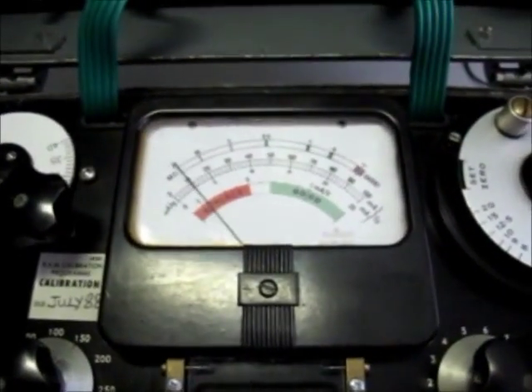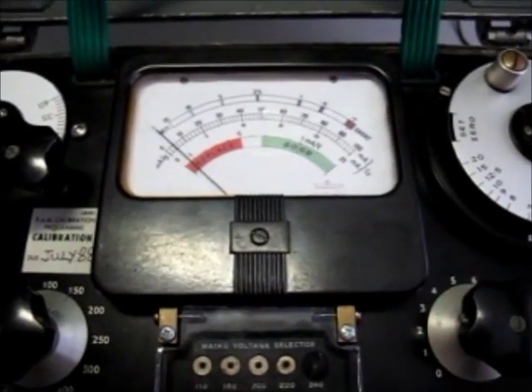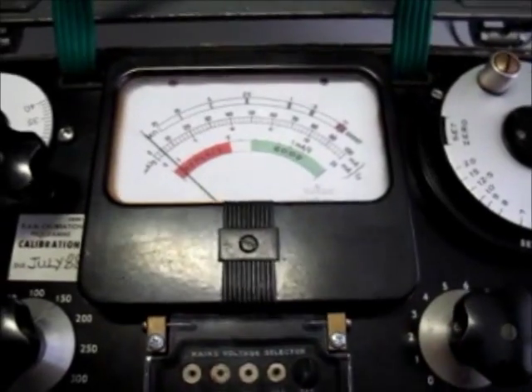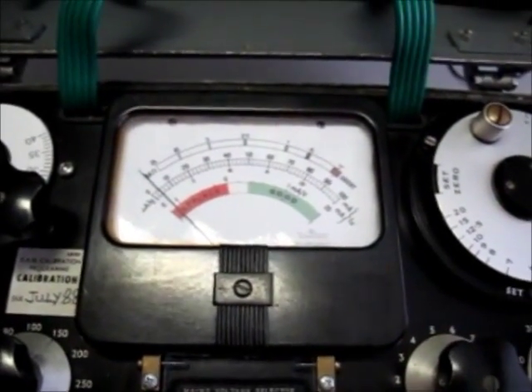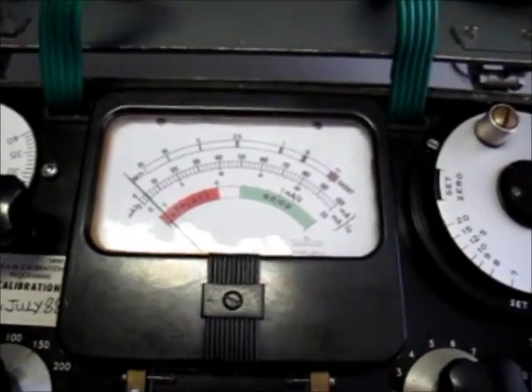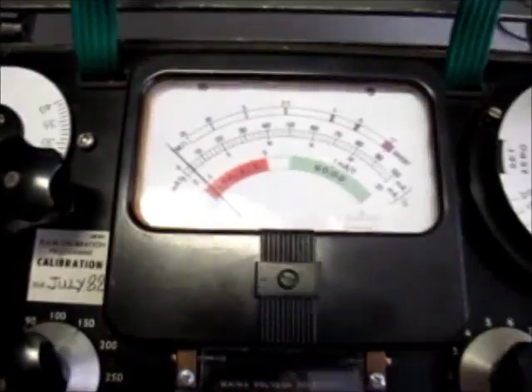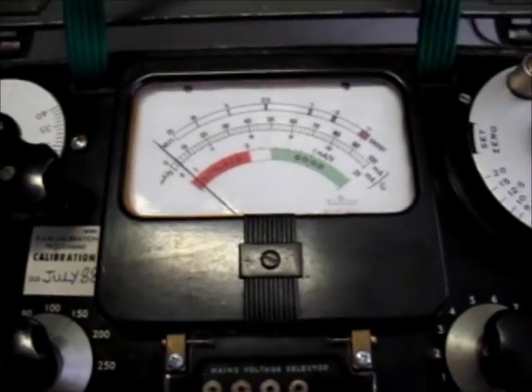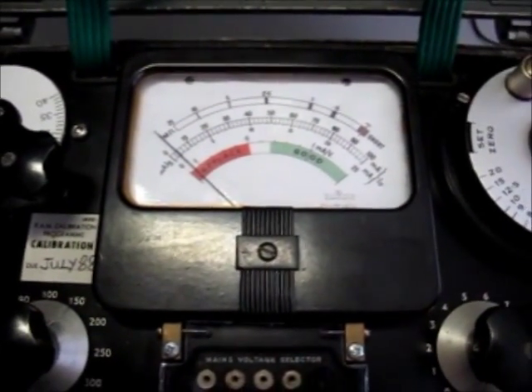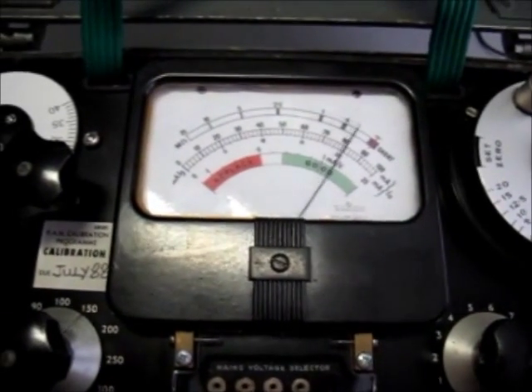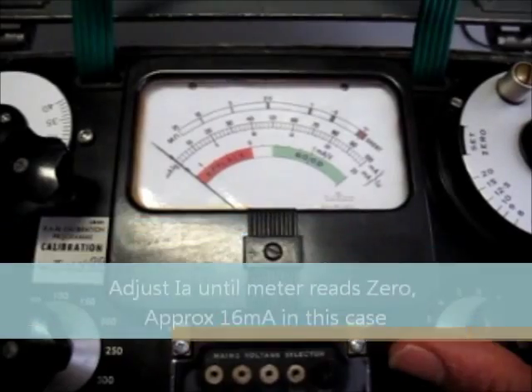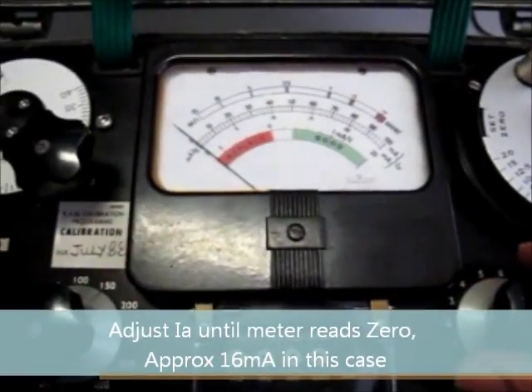We'll then go through a number of anode tests, and we'll try to make sure the meter stays higher than 25 milliamps. So all these are anode correction electrode to electrode tests. And finally we'll do a heater test. Now we're going to see the heater's now starting to come on inside. And now we're really going to do our test. Now the minute you kick to this section, the meter will go up or down, and you're meant to zero it. So we'll just go there, it's gone right over. We'll bring it down by adjusting the current. So we'll set it at zero.